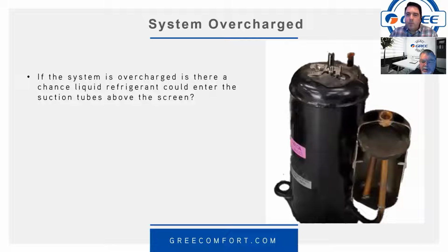But if it's overcharged, is there a chance that the refrigerant could flow in and go above that screen and then get sucked down into the suction side? Yes. And then you've got bigger problems than an E1. Most certainly. Okay.